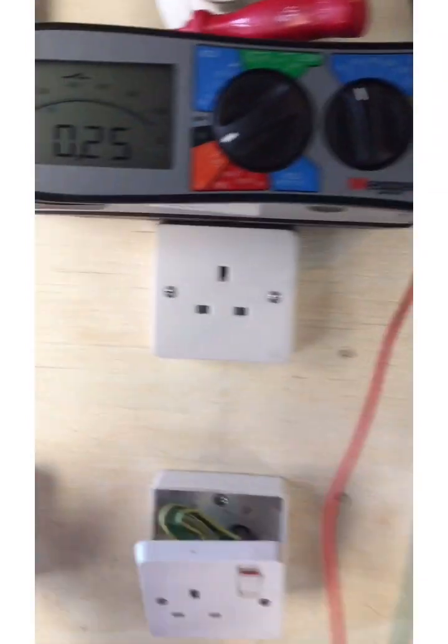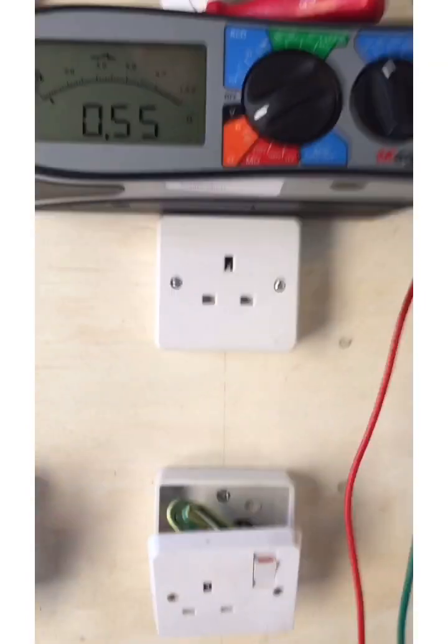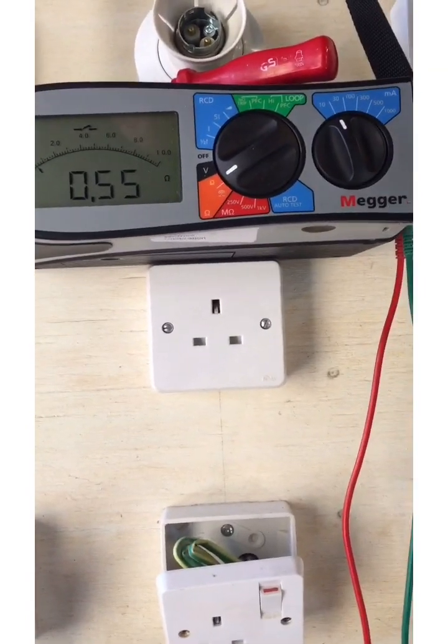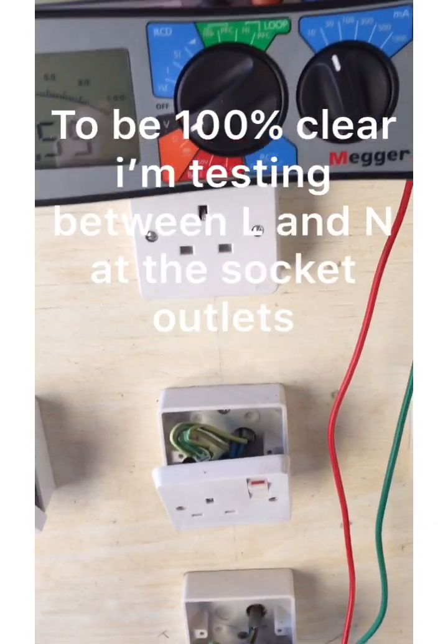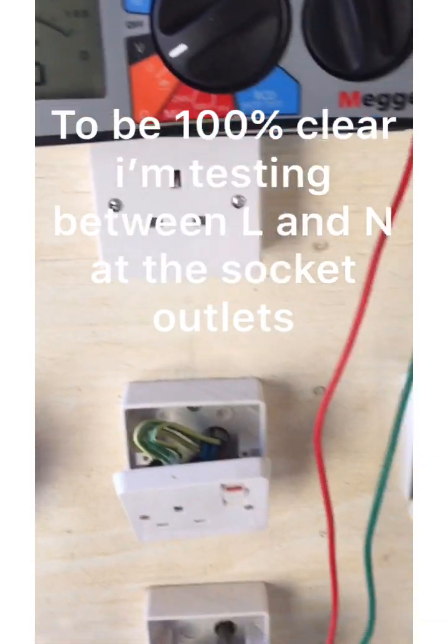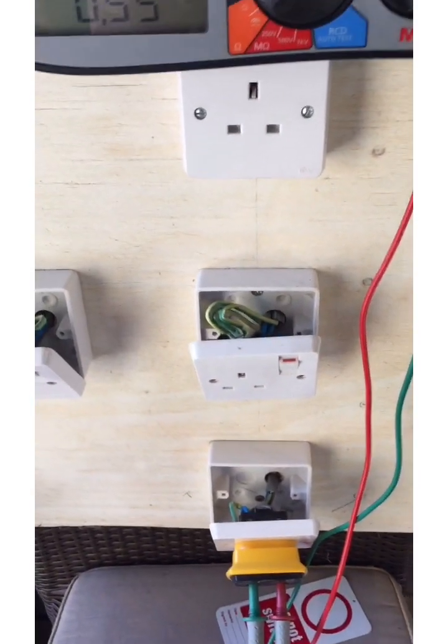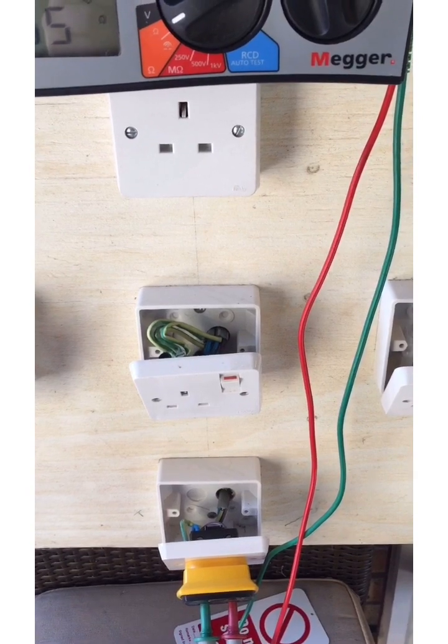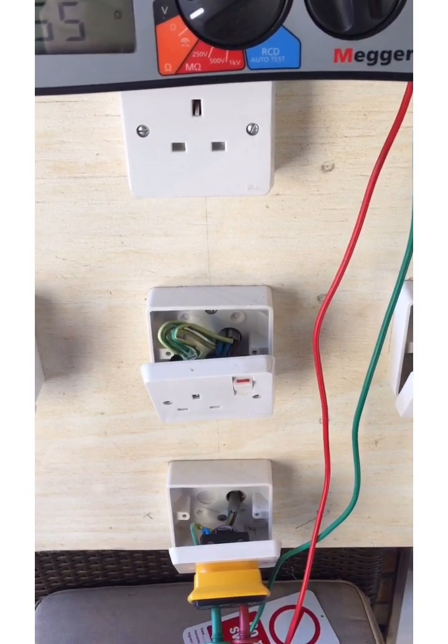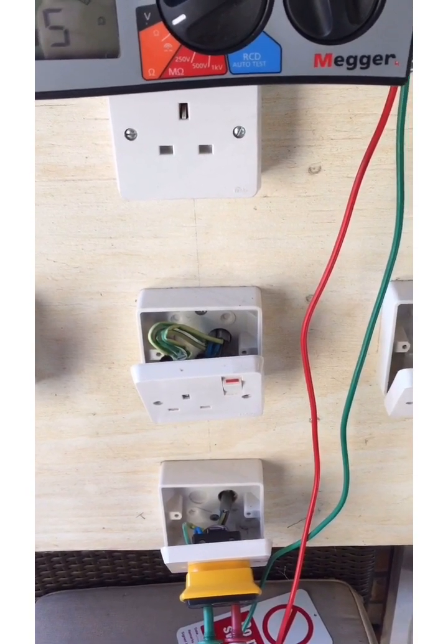Now if I go to the spur, what am I getting here? I'm getting 0.55, now I've got 0.58 before. Again, there or thereabouts. That's what we expect. We expect that the values across the ring main to be consistent and any spurs to have higher values. And it's the highest value which is going to come from a spur which we record.